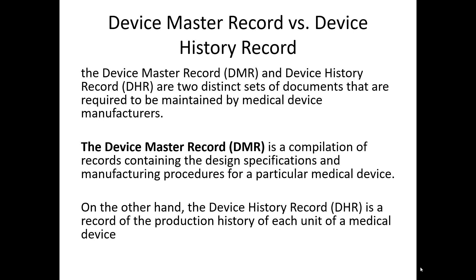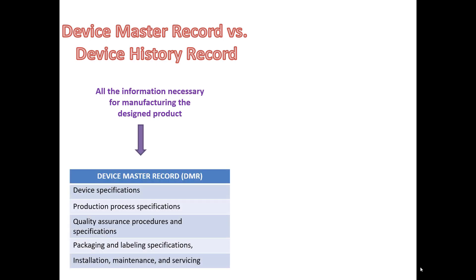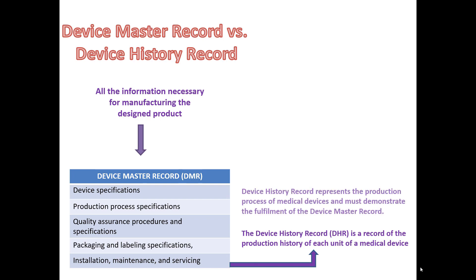Let's take a moment to recap the difference between a device master record and a device history record. The DMR and DHR are two distinct sets of documents — it's important to remember that — required to be maintained by medical device manufacturers. The DMR, the device master record, is a compilation of records containing the design specifications and manufacturing procedures for a particular device. On the other hand, the DHR is a record of the production history of each unit. All the information necessary for manufacturing the product is found in the DMR, and out of that comes the DHR.